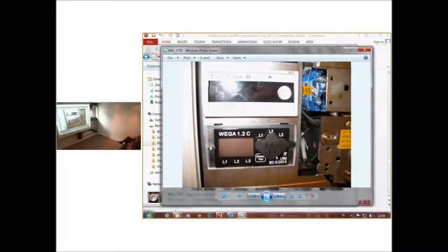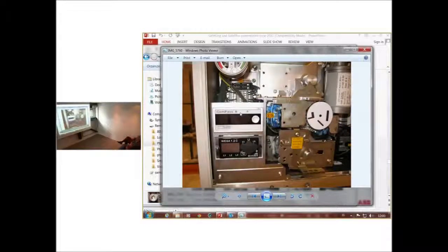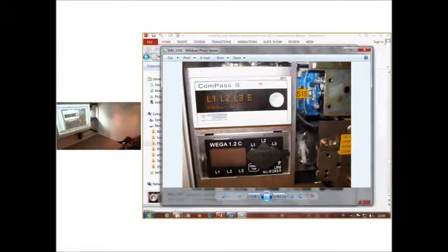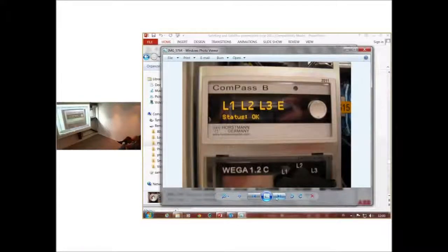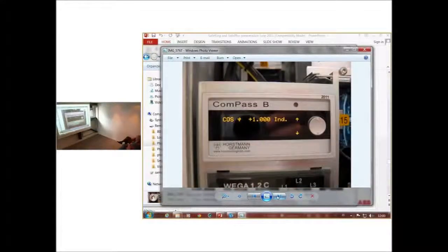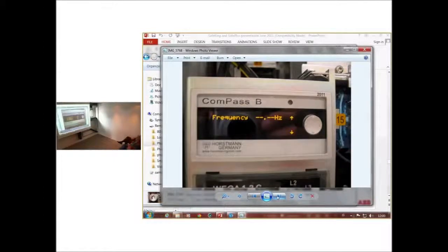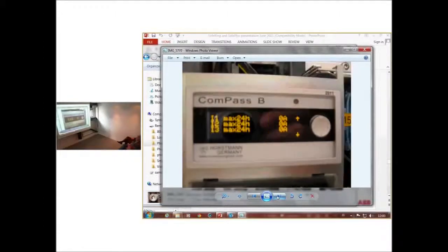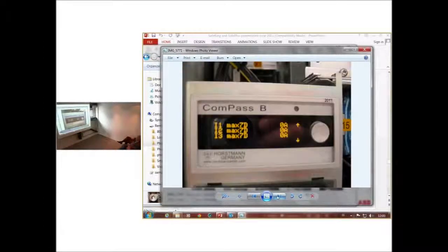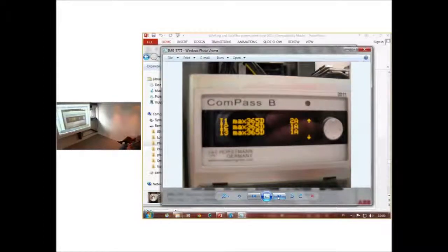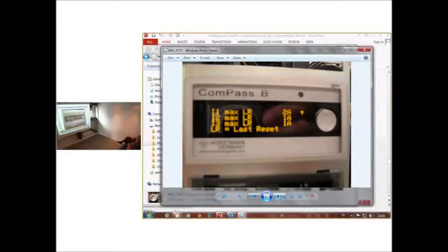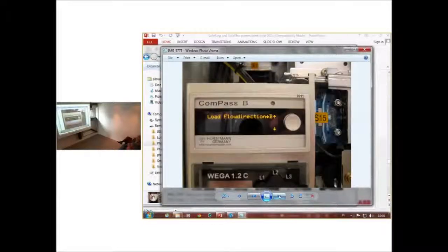And then you see this one is the capacitive voltage device, and then we use a Compass B device. And now you can read off L1, L2, L3, you can read off the voltage, you can read the current, cosinus phi and frequency, and averages every 15 minutes, maximum per day over 24 hours, maximum over 7 days, and per year maximum 365 days, and maximum after last reset, and the voltage and load flow direction.